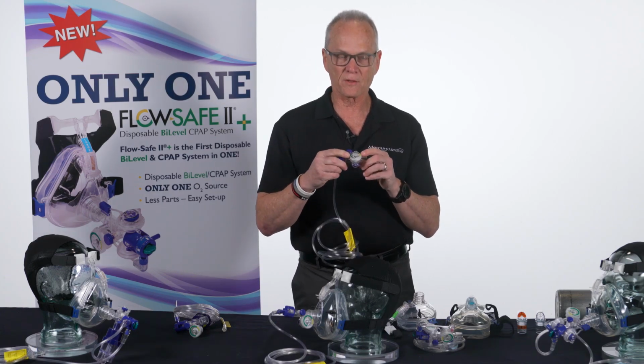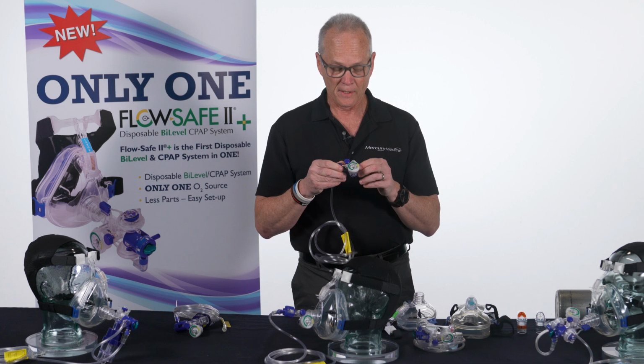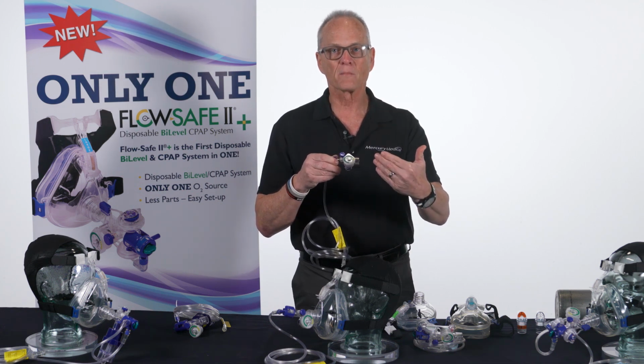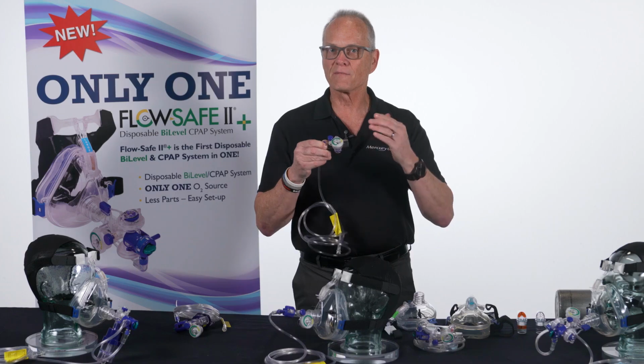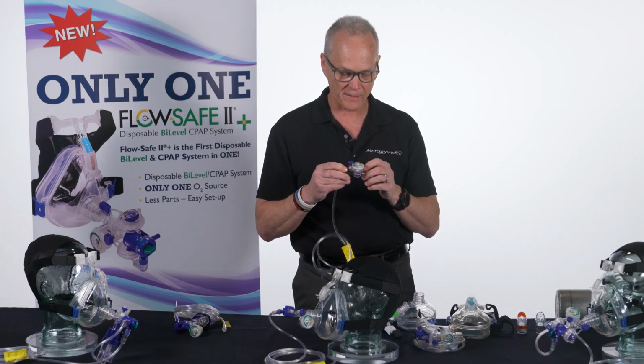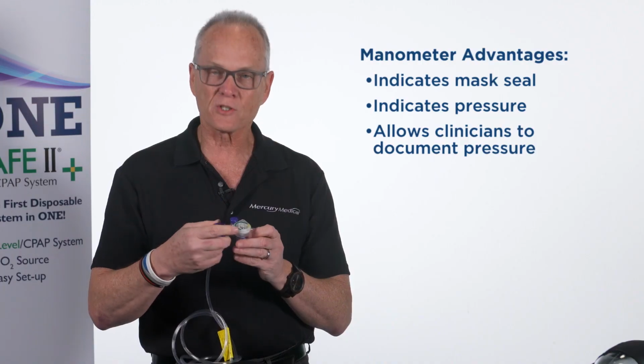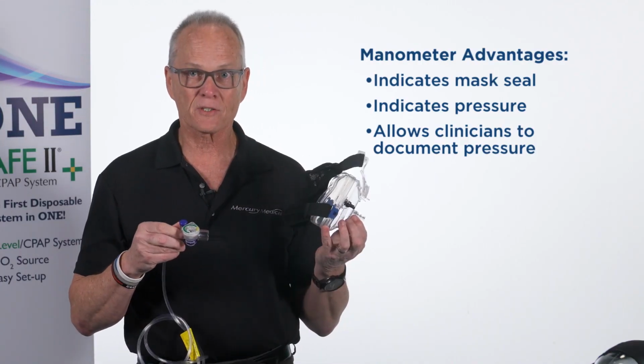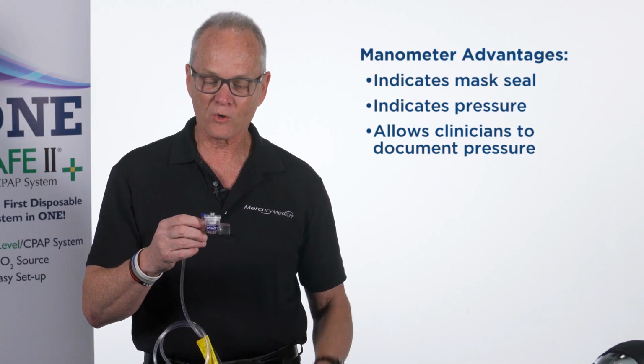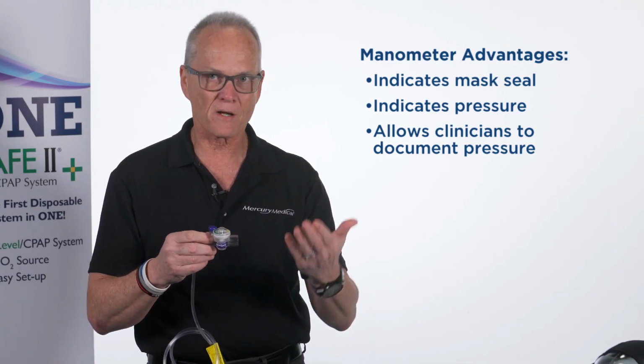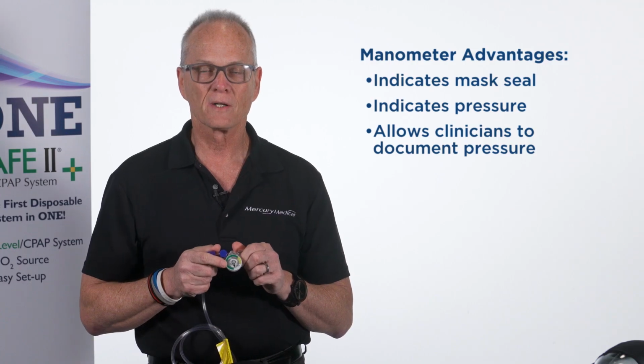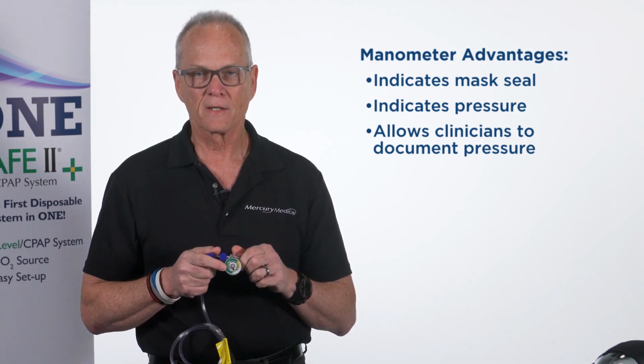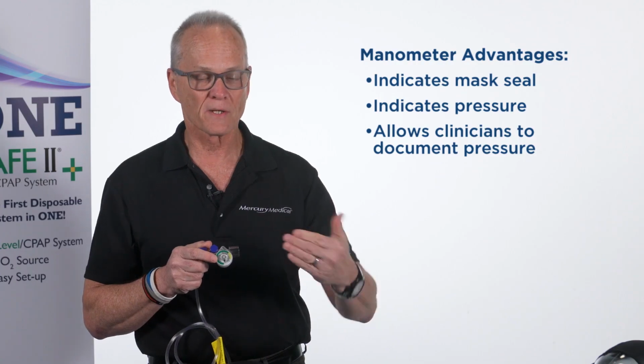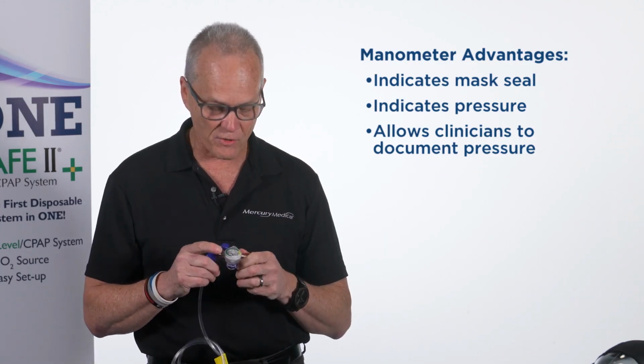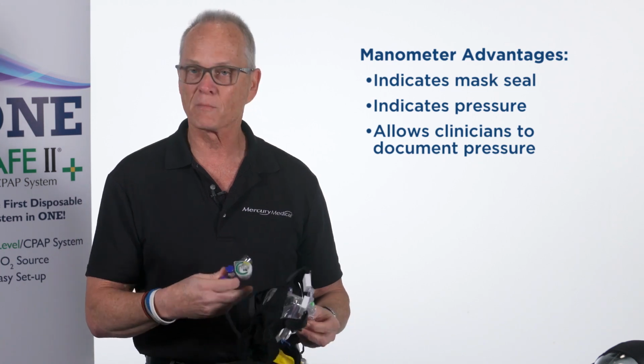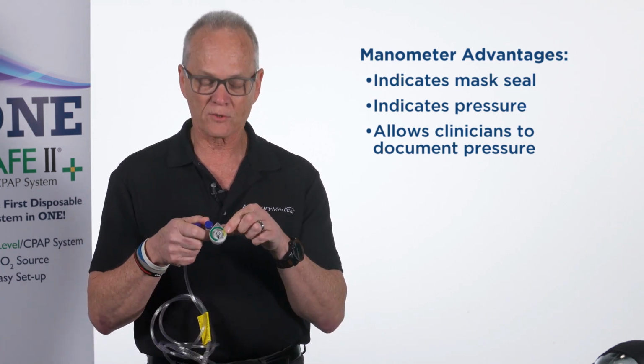So most people understand that pressure, and it's measured in centimeters of water. They understand the value of that, but sometimes this manometer is telling us a lot of information if we pay attention to what it's telling me. The first thing it's going to tell me, if it's not registering, then my mask is not giving you a seal. So if I turn the pressure on and I'm running the flow and I've got it on a patient and the needle is still sitting on 0, it's telling me right away that I don't have a seal. And in EMS and in some emergency departments, with the ambient noise that you may have in your environment, you might not hear a leak coming from a mask. So the visual cue is going to be in the manometer.